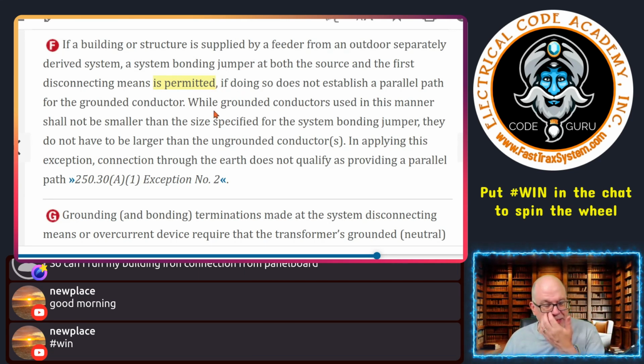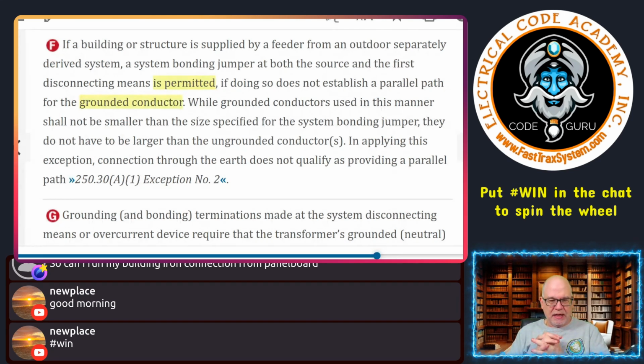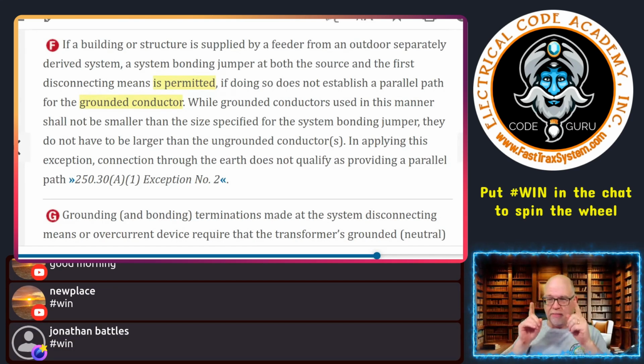So it's permitted to put that system bonding jumper outside at the transformer and inside as well. But if you do so, it does not establish a parallel path for the grounded conductor. And I'm not sure how that would do that, right? If you do it that way, you have to make sure, do I have mutual conductive paths for that grounded conductor connected at both ends? Is that going to create that, right? Now, if it does, then you have a problem because you can't establish those parallel paths. So you do what you can to remove that. So you choose which one you want to do. And like we said before, you can do it at the source or you can do it at the first means of disconnect. And that is where your GEC would go.